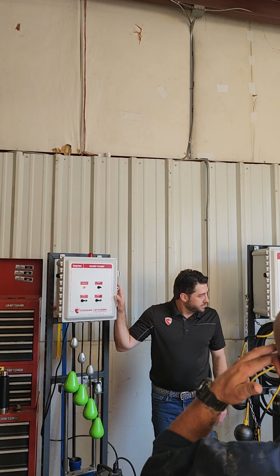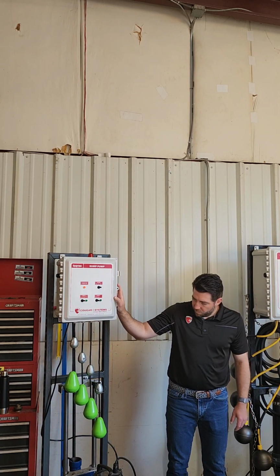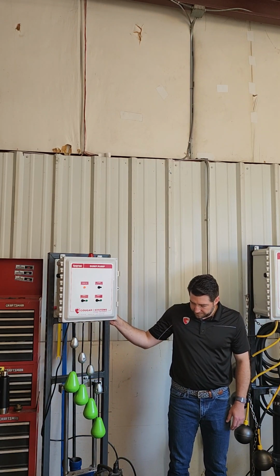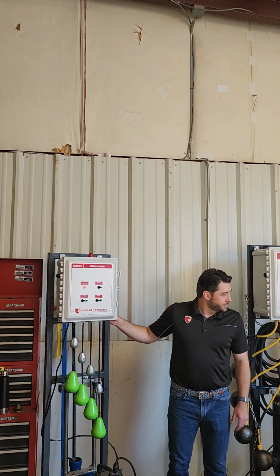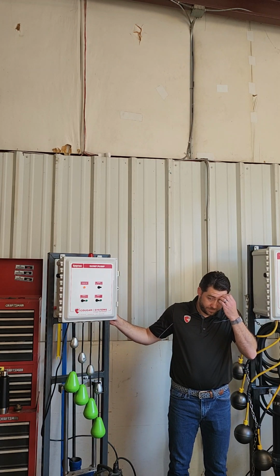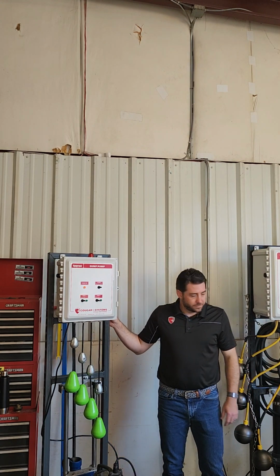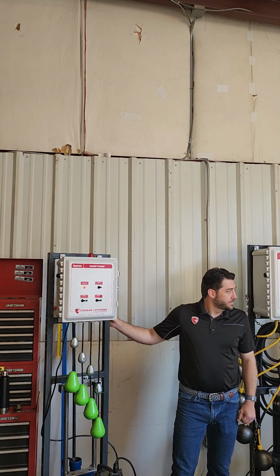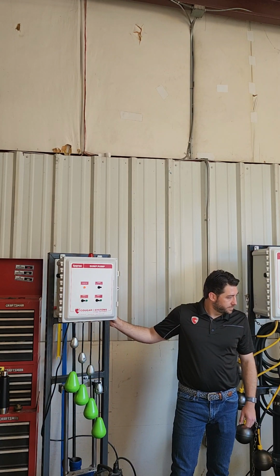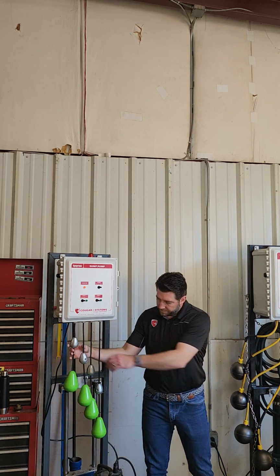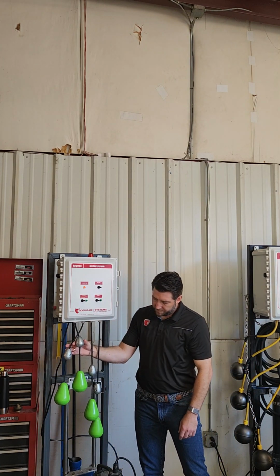Just on the floats, like you say, normally you've got companies that do the full float system, and the ones that do the maintenance is y'all, or the work. So you never want to show up to the pit full of crap. You want to be able to pump down all that. So instead of doing the off on lag alarm, do the off on alarm, then the lag.